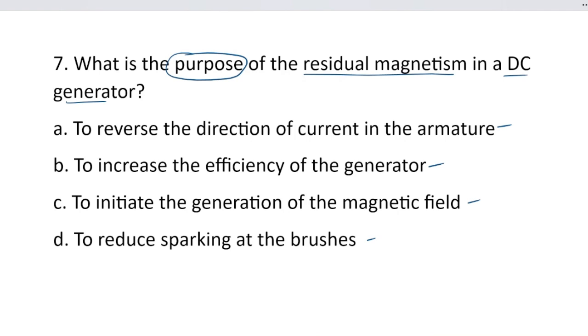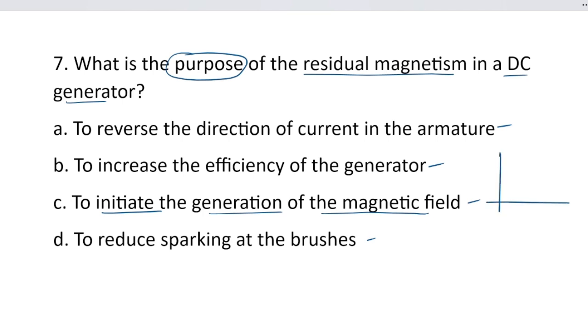Residual magnetism: when the supply of electricity is removed, the magnetic properties that remain are equal to the residual amount. Residual magnetism's main purpose is to initiate the generation of the magnetic field. Looking at the open-circuit characteristics — the E0 versus field current graph — the voltage starts at a value A2 even at zero field current, that starting voltage is the residual magnetism.